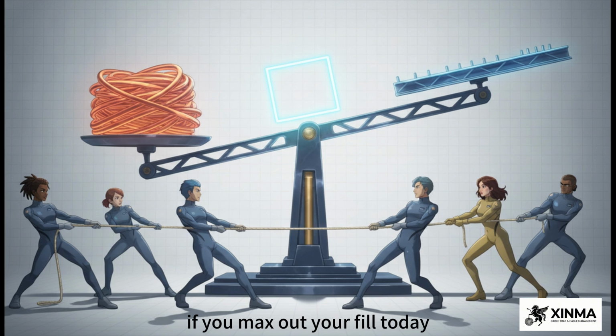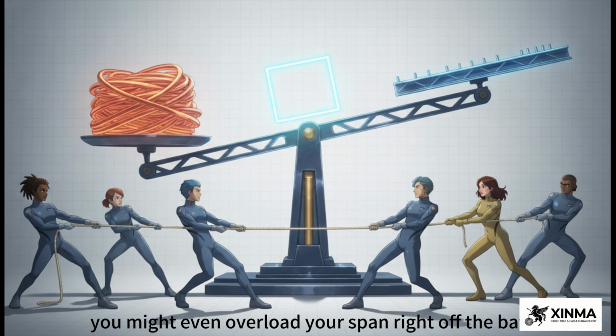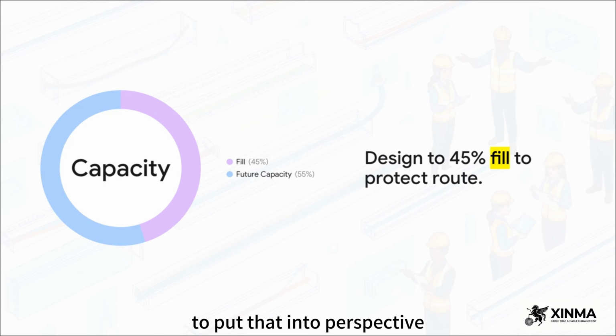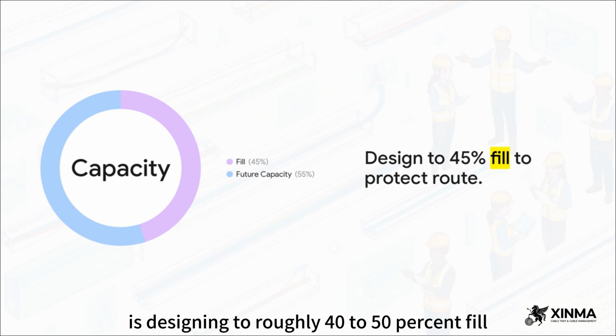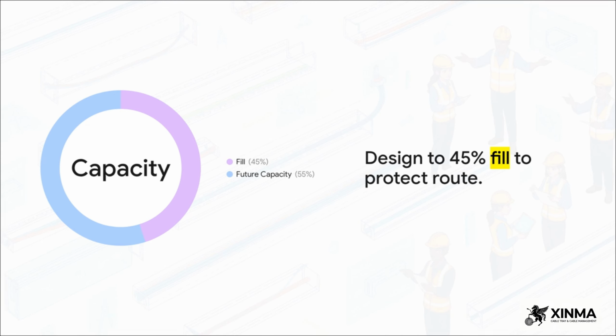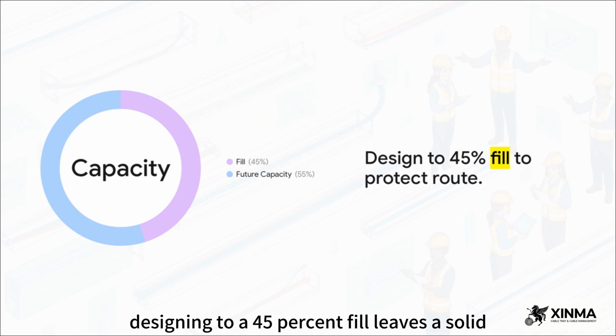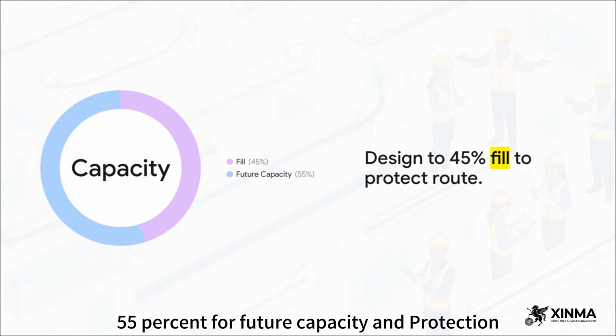If you max out your fill today, you completely ruin your future capacity, and you might even overload your span right off the bat. To put that into perspective, the golden rule of specification is designing to roughly 40 to 50% fill at commissioning. For instance, designing to a 45% fill leaves a solid 55% for future capacity and protection.